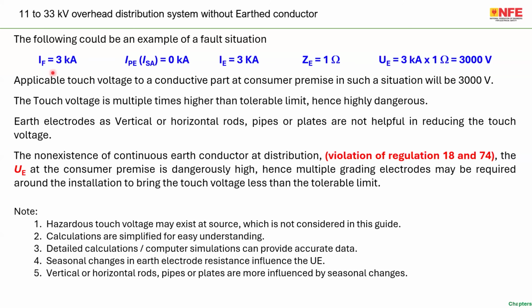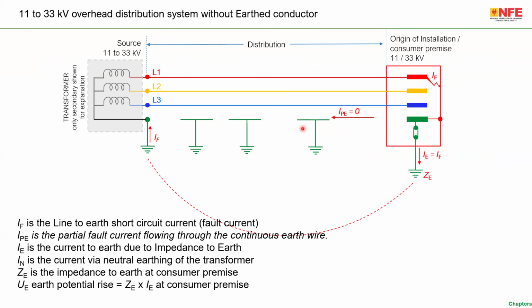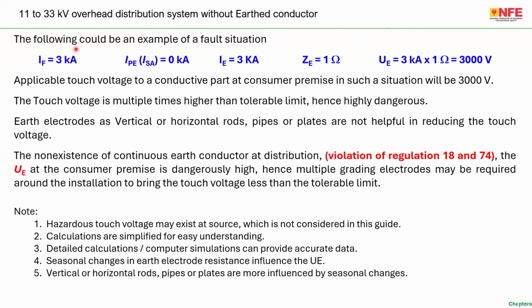I just put a very small arbitrary value. Imagine an installation without a metallic fault return path, and imagine the fault current is 3 kiloampere. So the current through the metallic fault return path is 0. IE, through the earth electrode, is 3 kiloamperes. Imagine the earth electrode resistance is 1 ohm. The potential gradient, the EPR, earth potential rise, is almost 3000 volt. This 3000 volt is many multiples of the tolerable limit, because the tolerable limit for 1 second disconnection is 115 volt, and for 0.1 second disconnection about 600 volt.